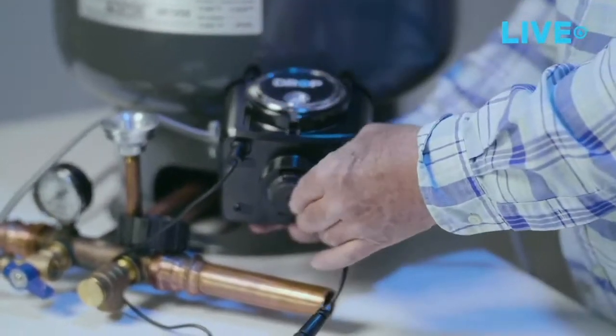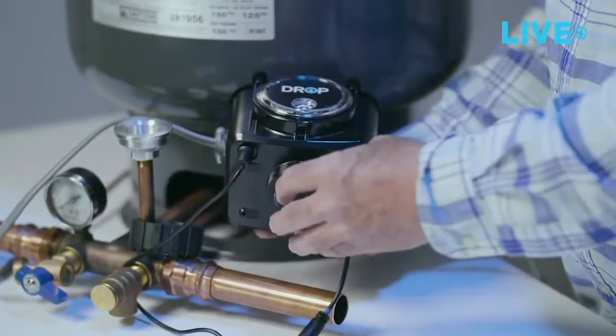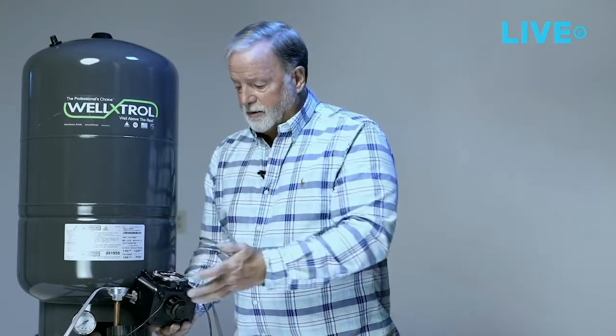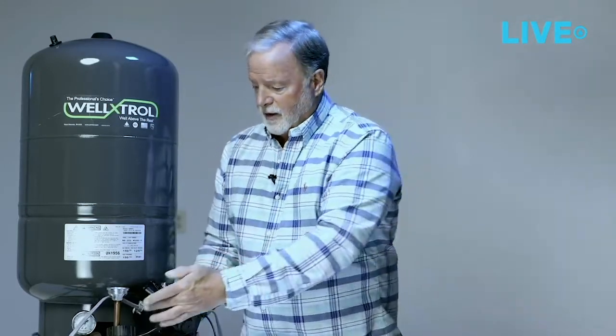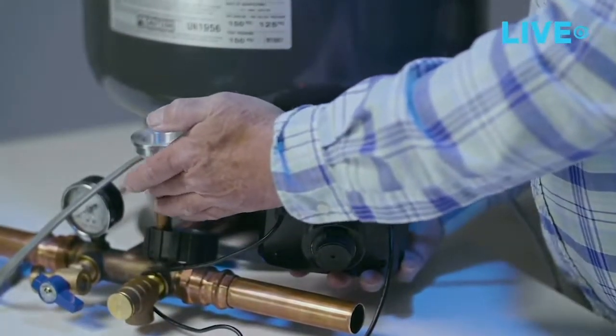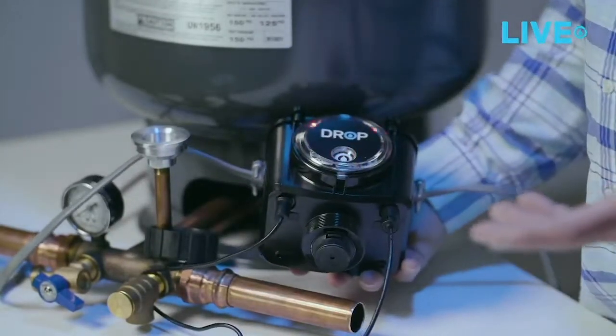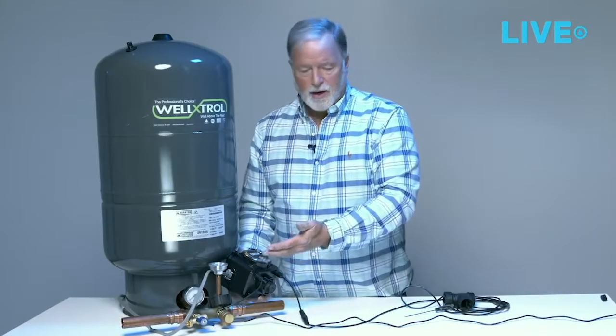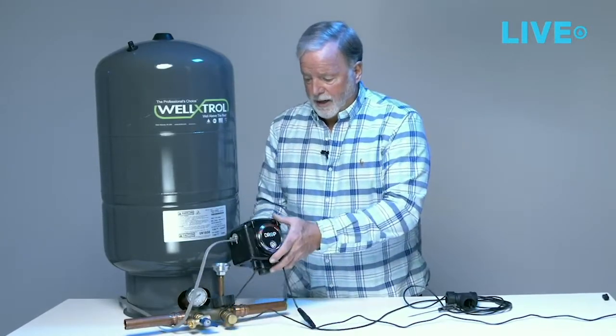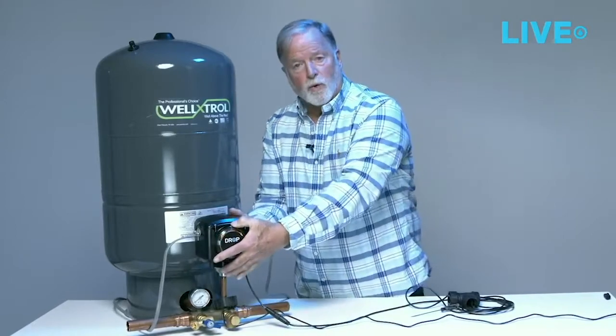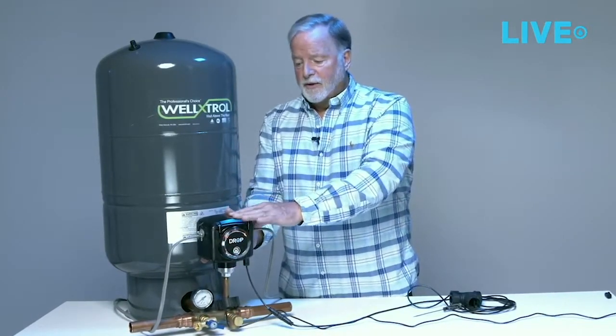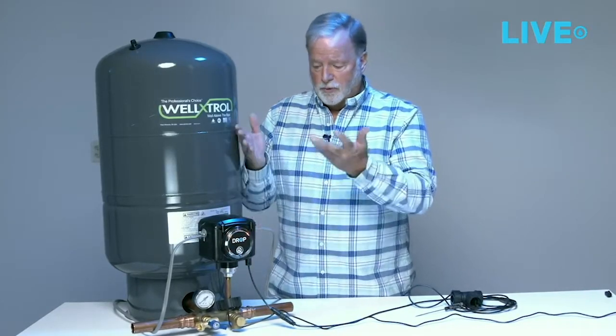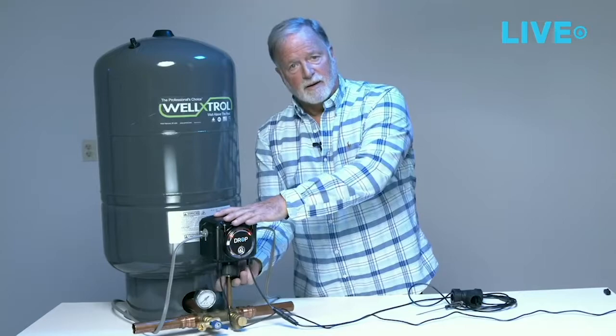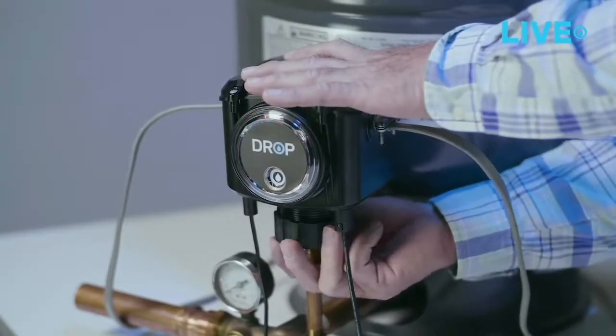And so this is a pressure sensing element that we make at CSI. It's totally designed for this system and it's completely serviceable. So just as quickly as releasing that union nut, you can get to the pressure transducer. And one of the reasons this is important is any pressure switch, the sensing connector here would tend to potentially over time plug up. And when these plug up with iron, calcium, debris, in any other pressure switch you would be forced to try to unwire it and rotate the switch off the nipple. In this case, you just merely release the union and pull it straight up. So we think that's a really neat service item feature that every contractor can enjoy.